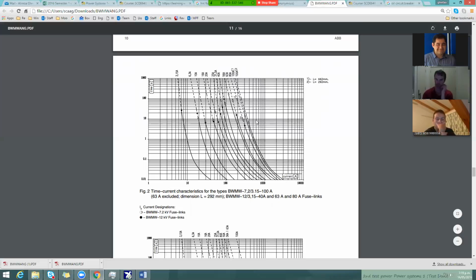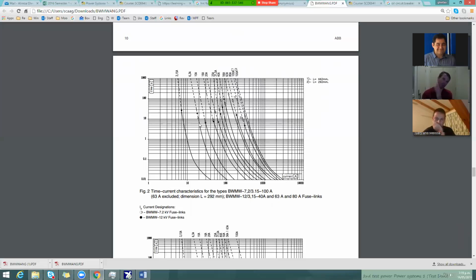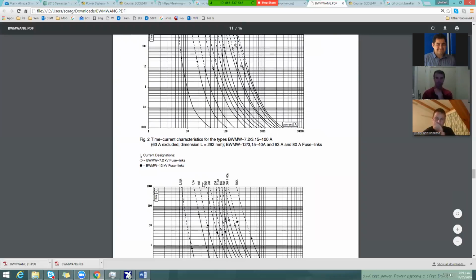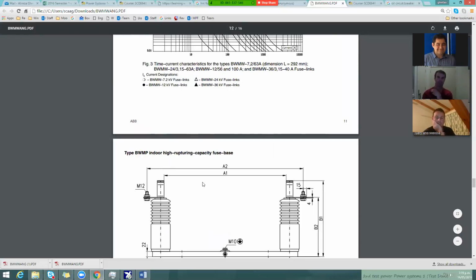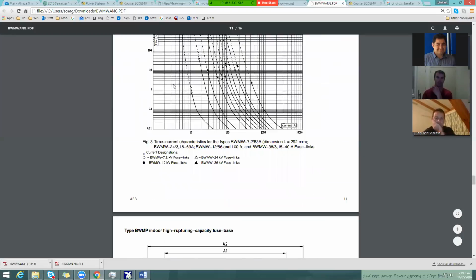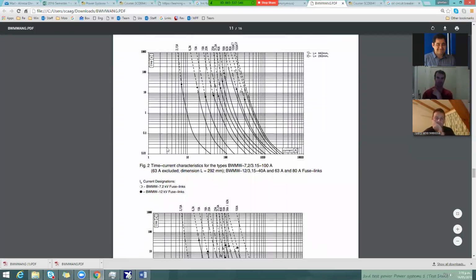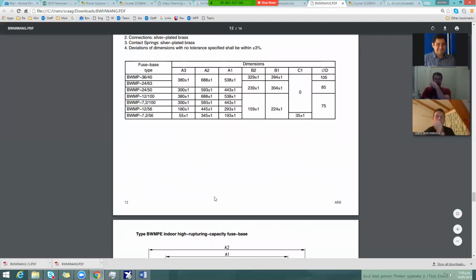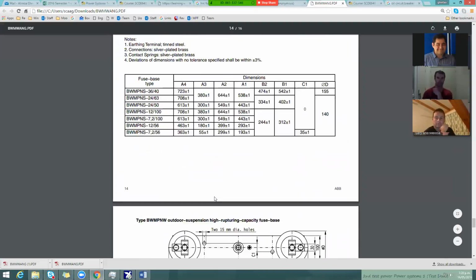So the nominal current definitely needs to be below the rated value of the fuse. And you also need to make sure that if you have inrush current, it can be handled. So we have different fuses, different types, and you can see different curves and other information for each.